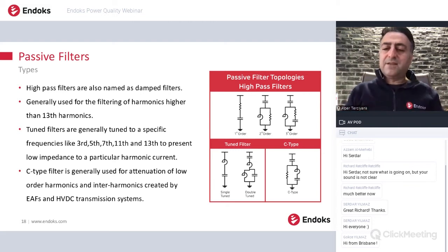So the series resonance frequency of the filter is the frequency which we would like to eliminate or filter out. There are some other filters, for example, double tuned filter or C-type filter. All these designs are actually used for, of course, the optimum solution. I mean, technical and commercial.